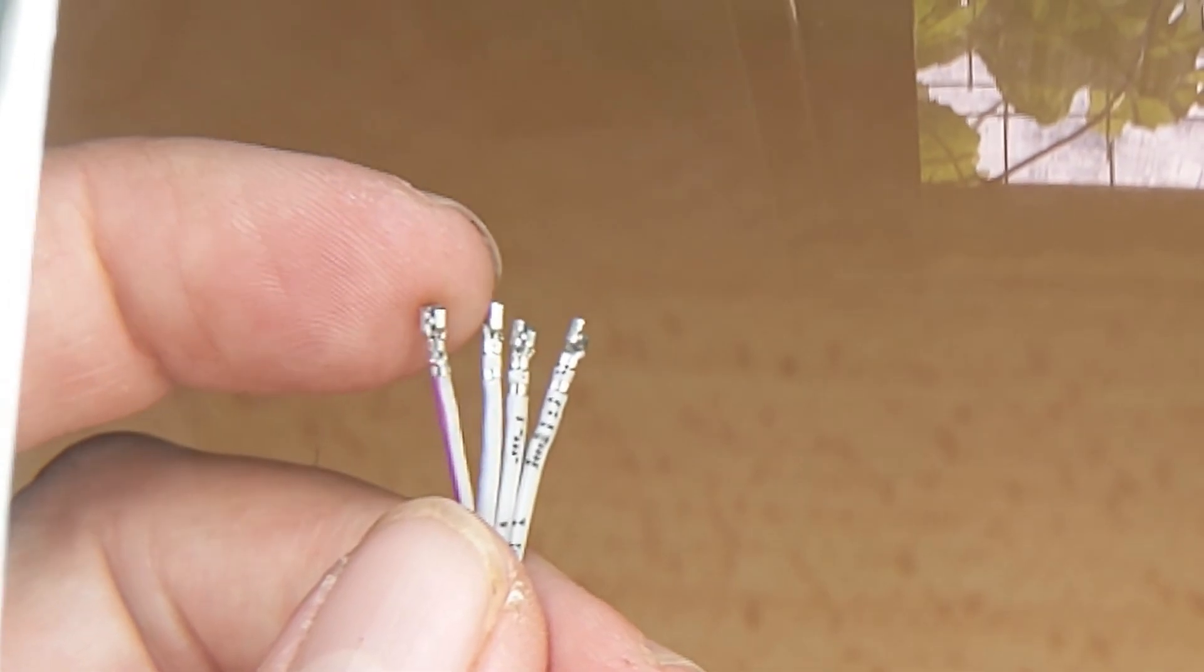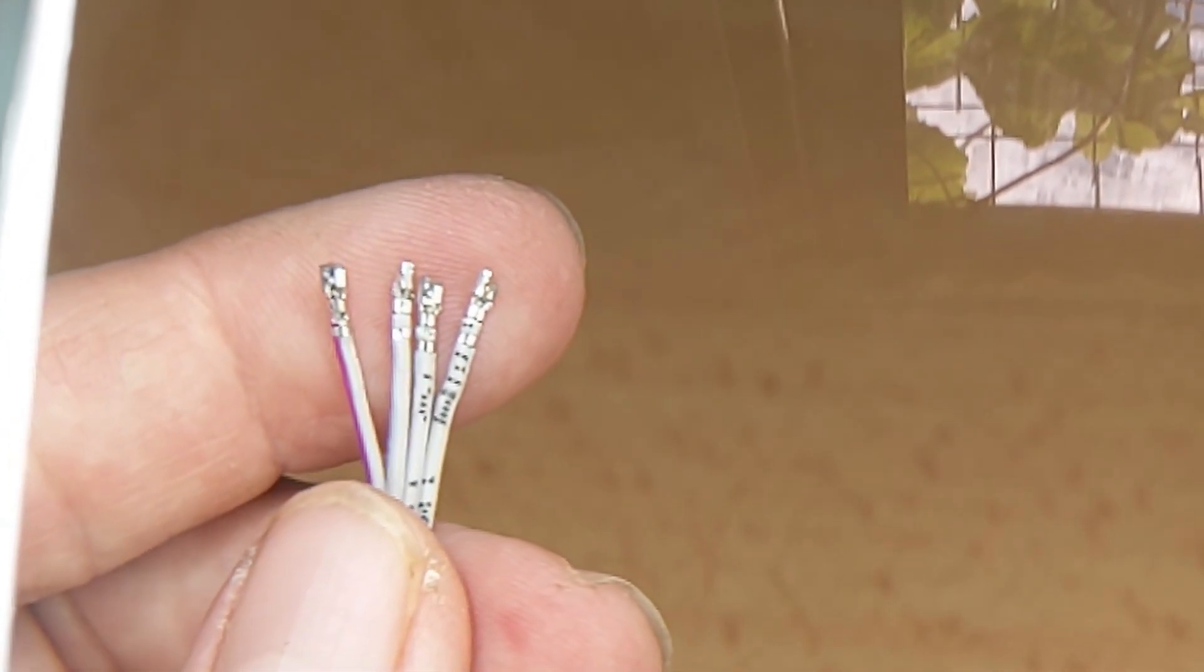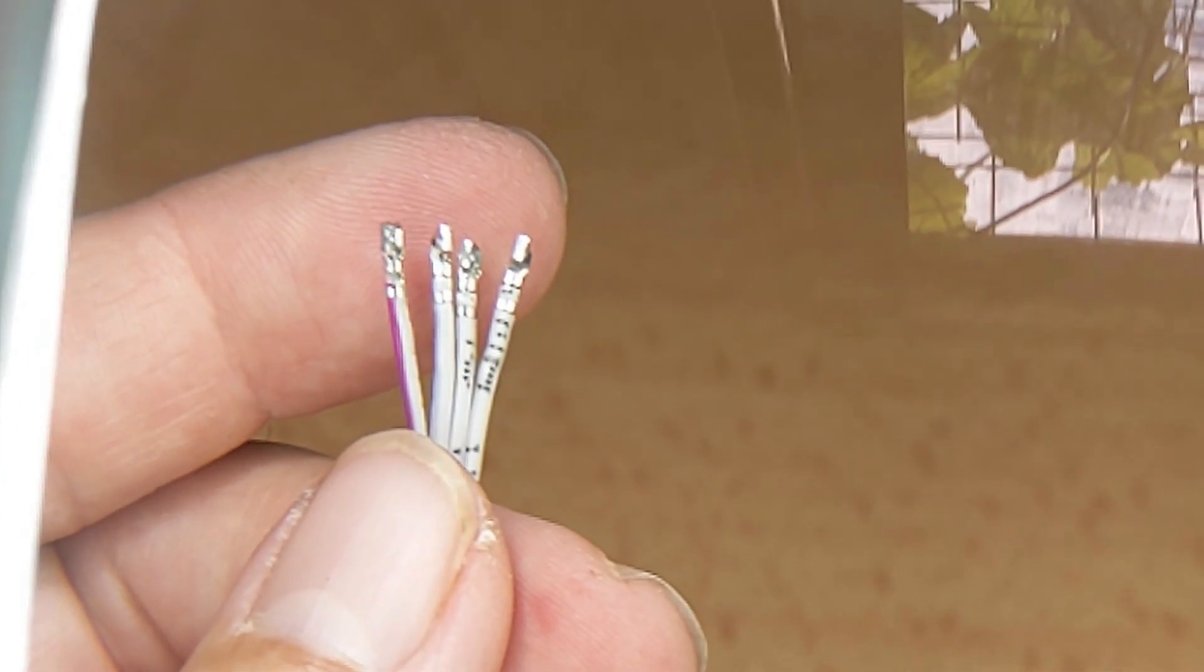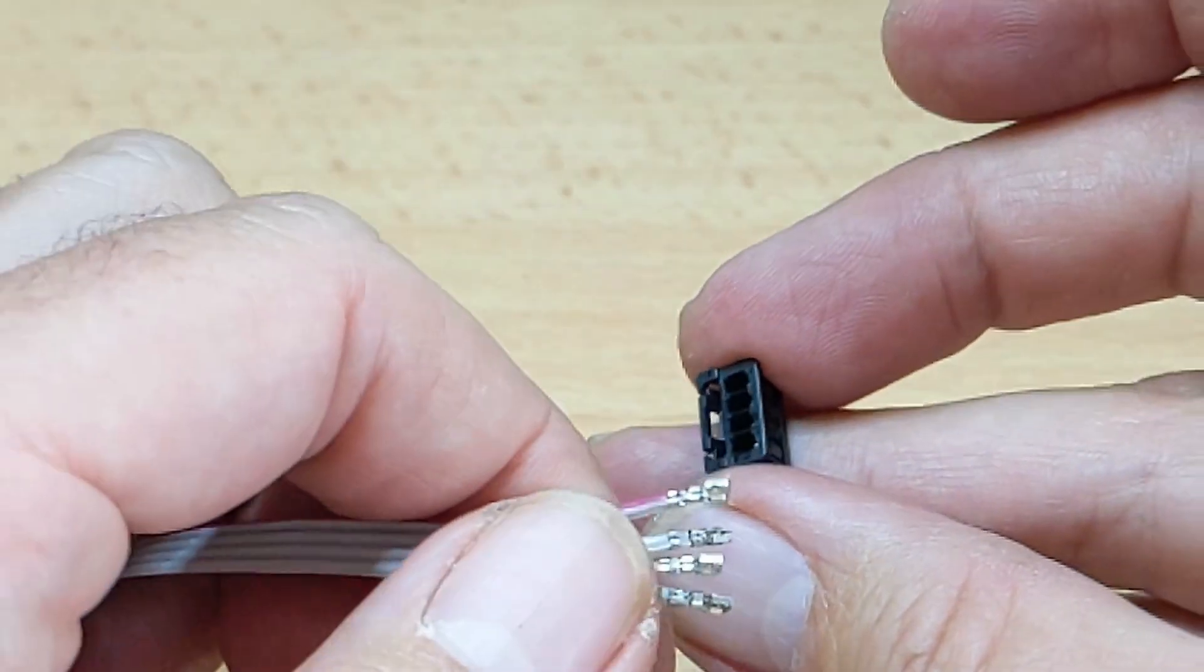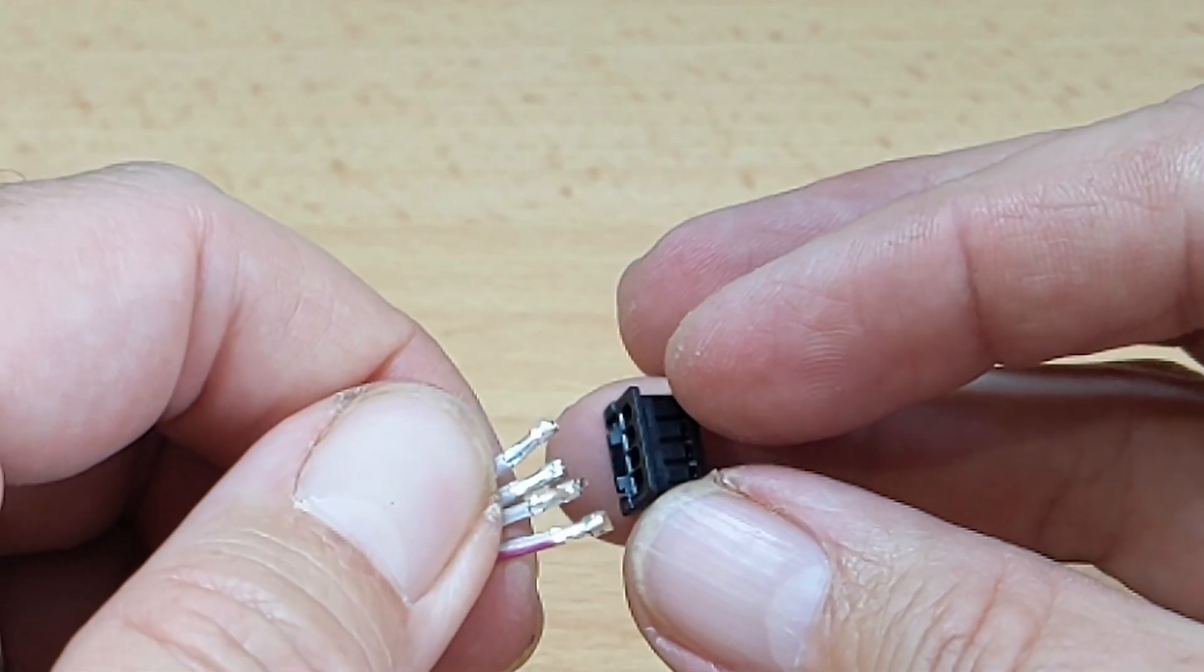Here we're looking at them through the magnifier hopefully you can see them there and so what we're looking for is no insulation in the second crimp and pulled on them and they didn't come off.